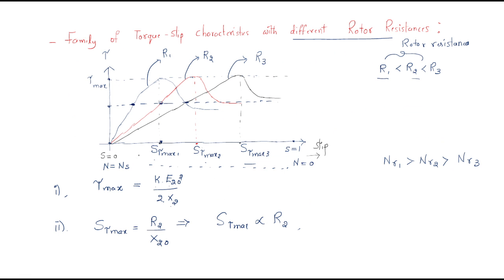This is about the family of torque-slip characteristics with different rotor resistances. When rotor resistance increases, the linear stable region increases and slip at maximum torque increases, but the rotor speed decreases and the operating point moves away from synchronous speed. The disadvantage is that copper losses increase and machine performance decreases. To maintain performance, rotor resistance should be kept as small as possible.